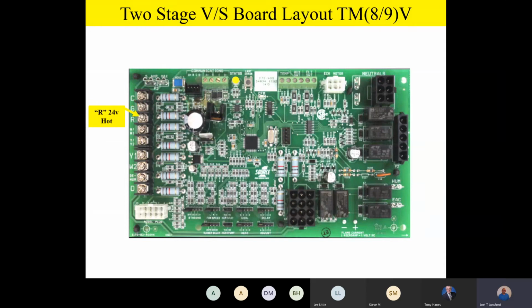On this board, because it's a two-stage heat, two-stage cool board, your W/W1 is your first stage heating call. And just like before, remember, team, if you're stuck with a single stage thermostat, don't forget to land your heating W terminal on that W/W1. But if you have a two-stage thermostat, your first stage heating, W1, lands on that terminal. Y/Y2 is your second stage cooling call.